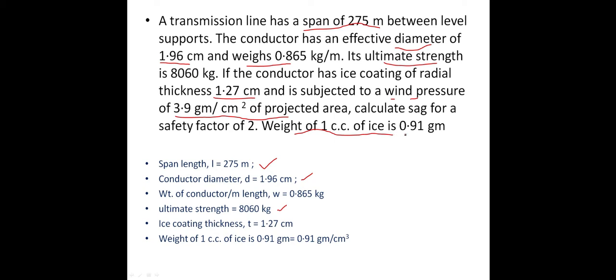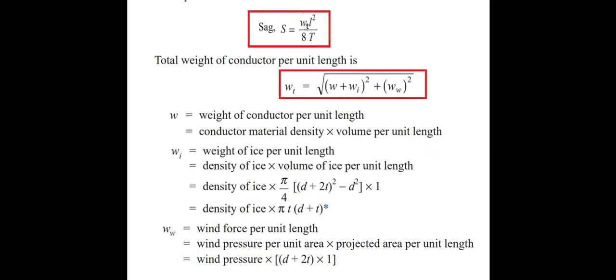Weight of 1 cc of ice is 0.91 gram — cc means cubic centimeter. They may also give it directly as 0.91 gram per centimeter cube. The SAG formula when wind and ice are present is: S = (Wt × L²) / (8T), where Wt is total weight. The total weight formula is: Wt = √[(W + Wi)² + Ww²].